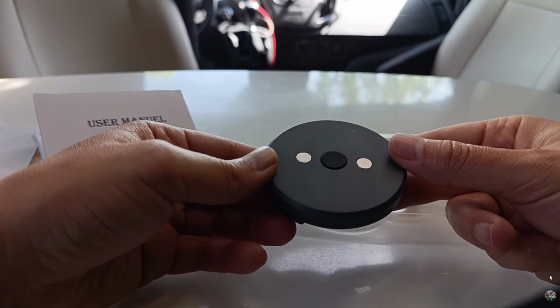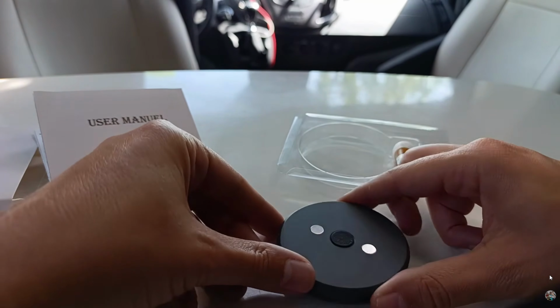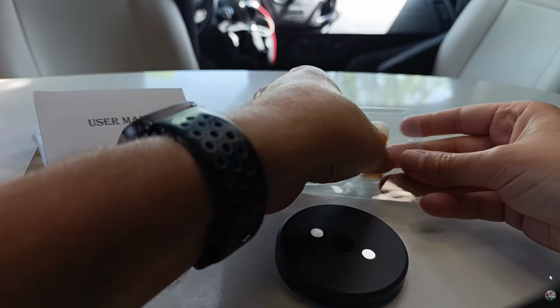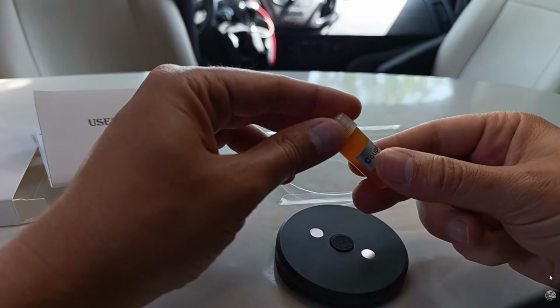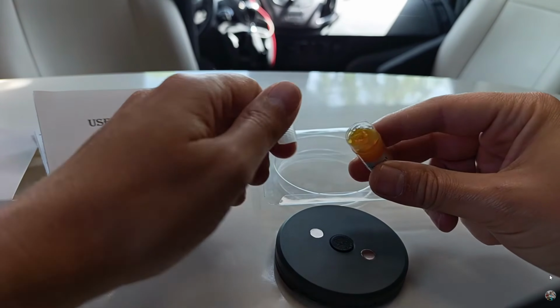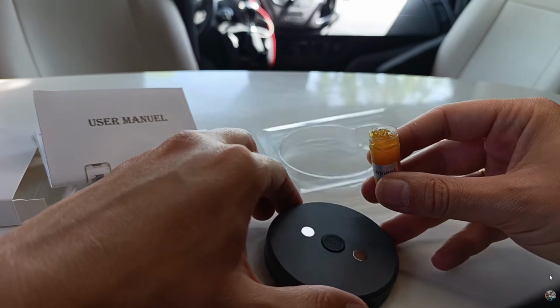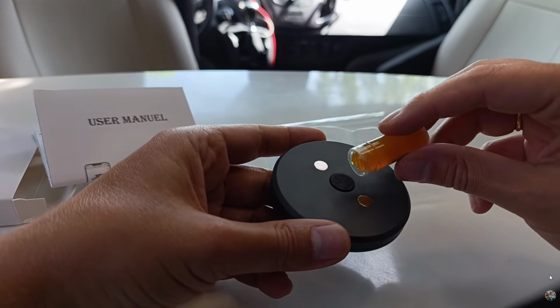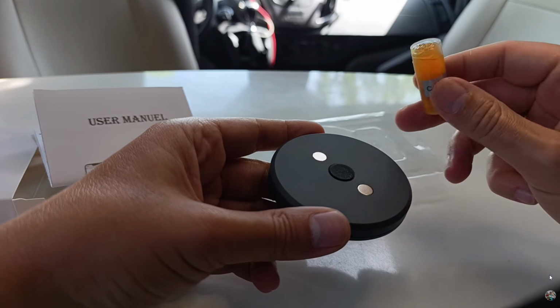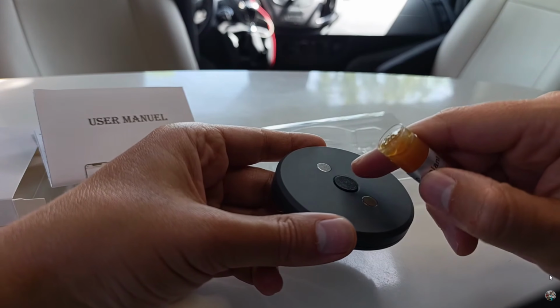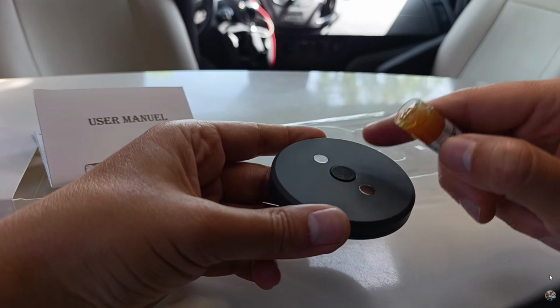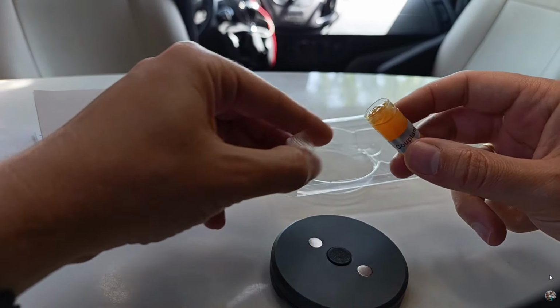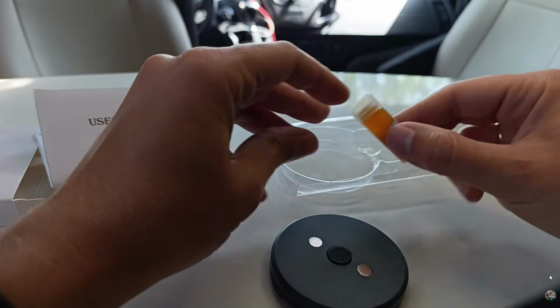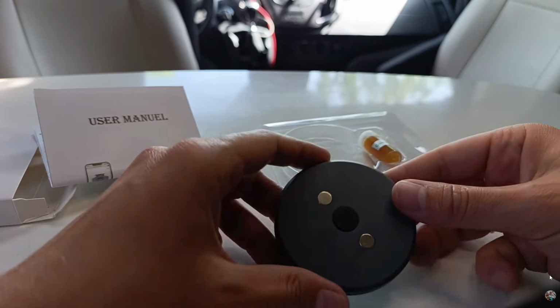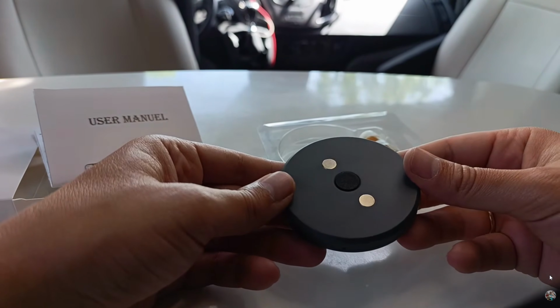This sensor costs less than €25 and supposedly does the same job, and so far it is giving us fairly consistent readings in several different cylinders we have tested. It comes with a liquid or paste that we must pour into the sensor before placing it in the cylinder. It is a coupling paste that helps the sensor read correctly, eliminating the air between the sensor and the metal, and with the amount needed in each cylinder, we have it for many years.